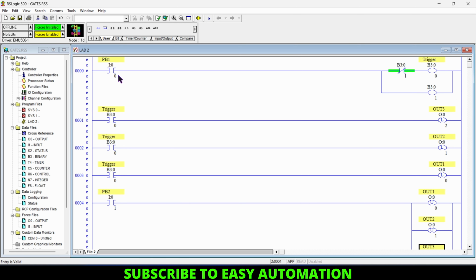Now I have addressed all the instructions in this program. I used this input address for the first push button, this input address for the second push button, and these three latch instructions for our output addresses. And I have created one trigger pulse here, which will be used for turning on these outputs. If you look closer in this program, you will find one problem here: whenever we give the trigger pulse from here, the trigger pulse will come here, and it will turn on all the outputs at a time.